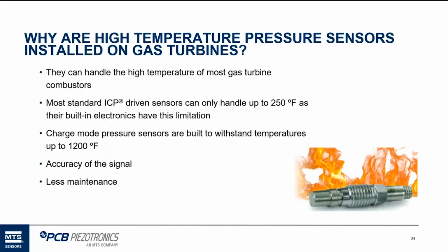Again, recap, why are high temperature pressure sensors installed in gas turbines? They can handle the temperature of most combustors, and depending on the mount, I don't think there's any combustor today that we can't mount one of our sensors on. I've never seen any go really above 12 or 1300 degrees. So, we have ICP style of pressure sensors, but they can only handle 250 degrees. So that limits the installation of where it can be. The signals, most accuracy of the signal is with a high temperature sensor mounted directly onto the gas turbine. And the maintenance is a lot less than the other style of sensors that we talked about, the remote and the close coupled sensors.